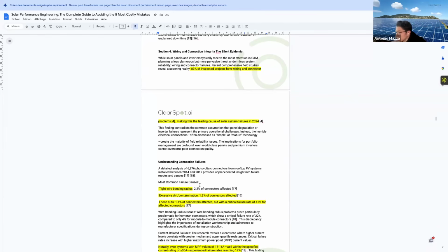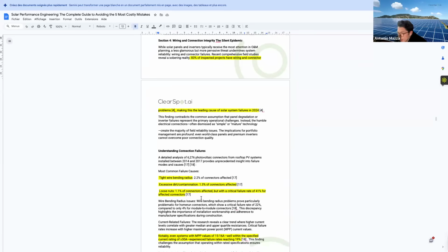Most common failure causes: tight wire bending radius, affecting 2.2% of connectors; excessive dirt and contamination, affecting 1.3% of connectors; and loose nuts, affecting 1.1% of connectors, but with a critical failure rate of 41% for affected connectors.